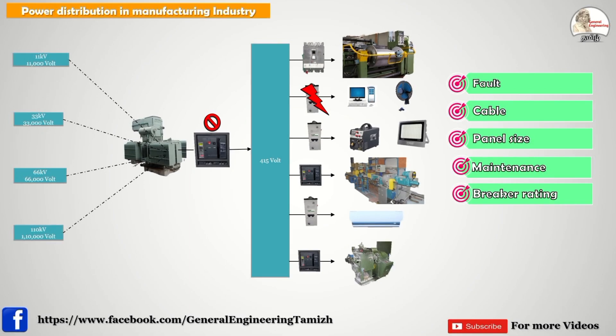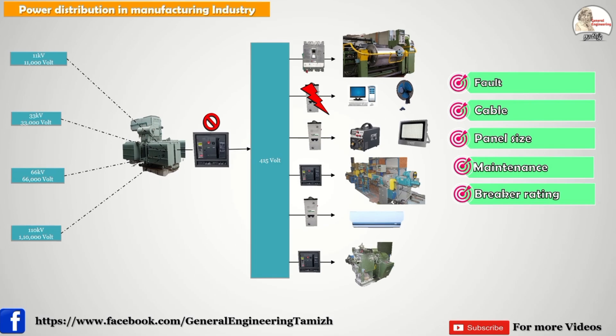The next scenario is breaker rating. Different types of breakers — MCB, MCCB, ACB — are all in one panel. For ACB and MCCB you can choose a current tripping setting, but MCB has a fixed rating only. So your required protection setting is not possible in this system.